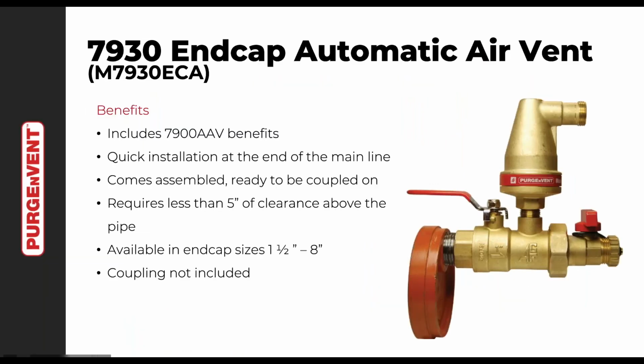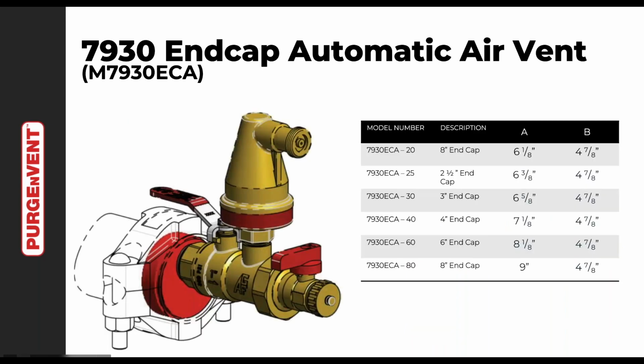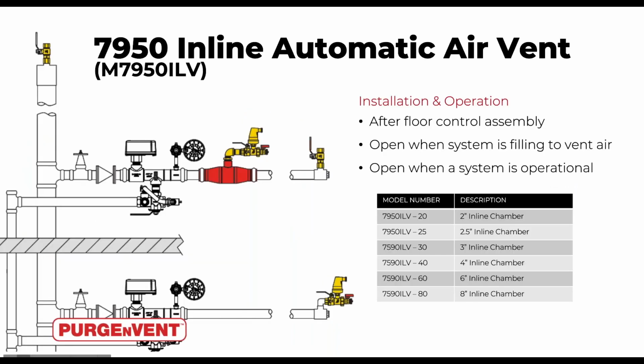Now, specifically for distribution centers, we had one very large contractor that was doing distribution centers around the whole country. And when you're doing large distribution centers, you have to be careful about the ceiling spacing from the top of the pipe to the bottom of the roof deck. So we created the model 7930 end cap, and this allows for the installed height of the product to be below 5 inches, which keeps it well within the ESFR requirements for distribution center sprinkler heads. So it's far and away the most compact device out on the market.